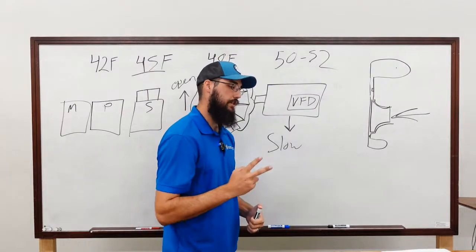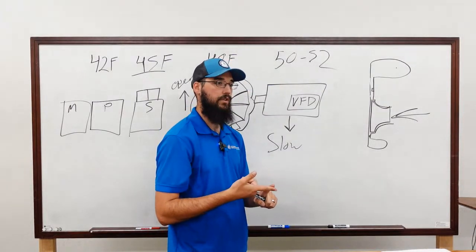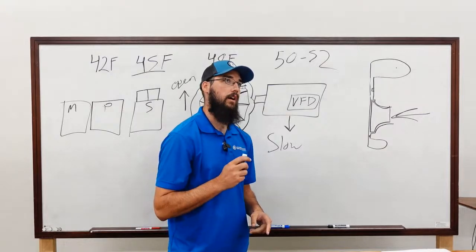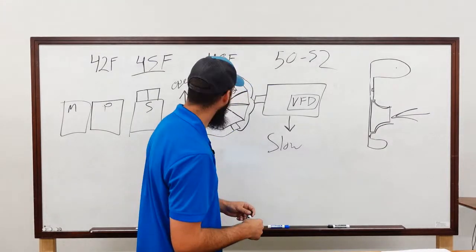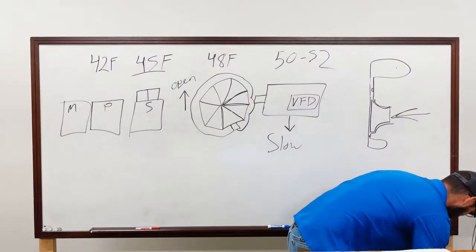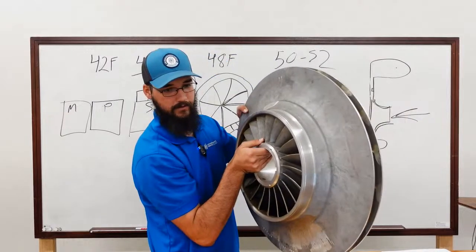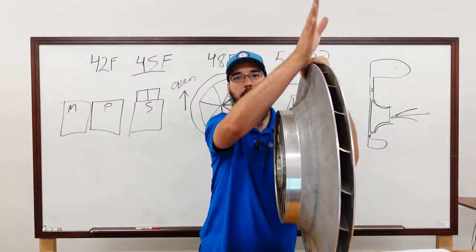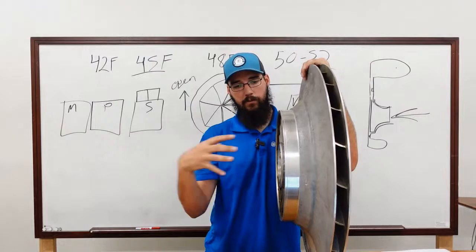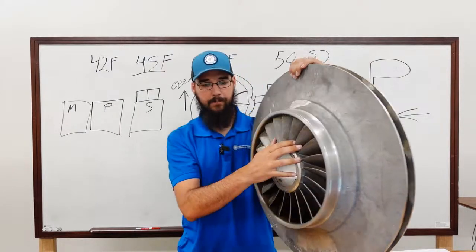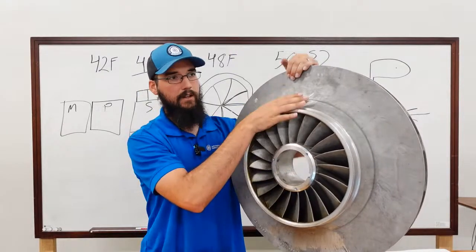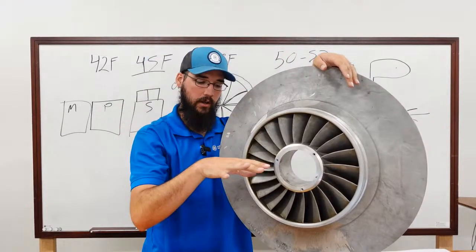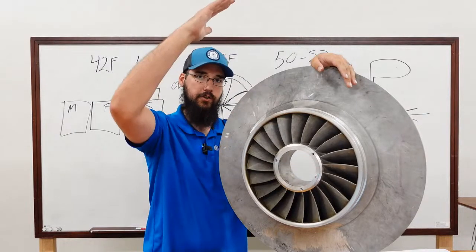So you have two conditions. You have a stall, which then leads into a surge. A stall will precede the surge. A stall can happen one of two ways. To represent this, I'll just use the impeller. We've been looking at it from this way pretty much all night, nose cone coming out into the diffuser assembly. As we're feeding this impeller, we can create so much differential across it, from the nose to the out, going into the diffuser and the volute, meaning the difference between suction pressure and discharge pressure becomes too great.